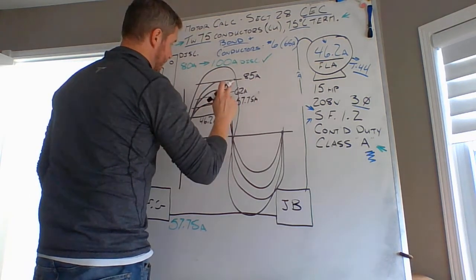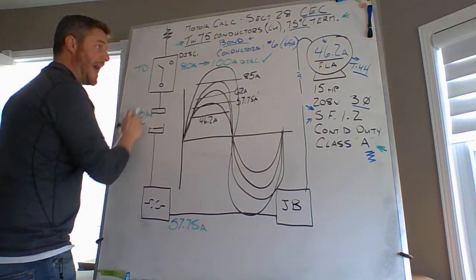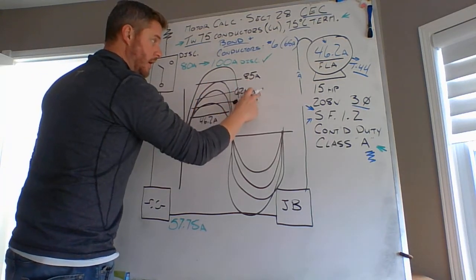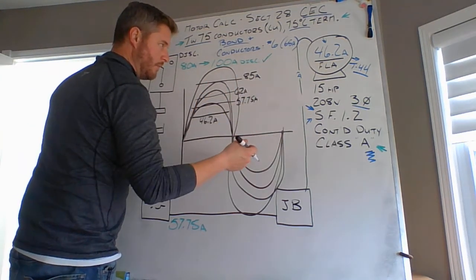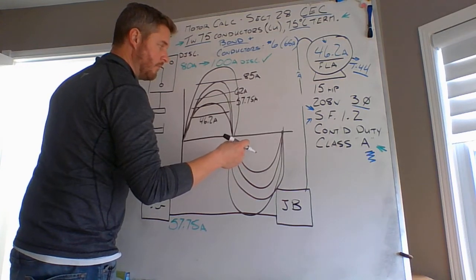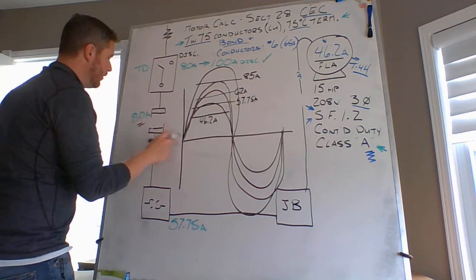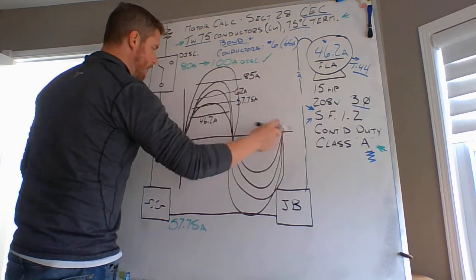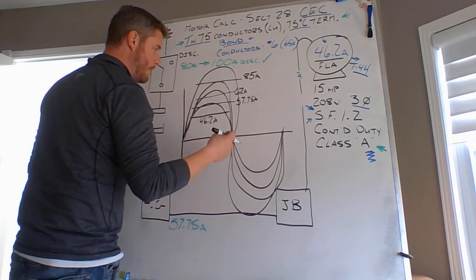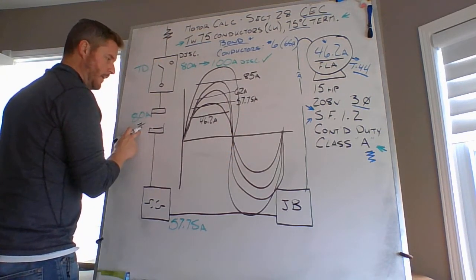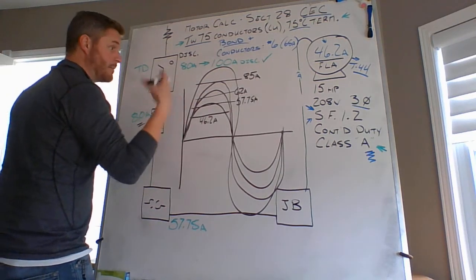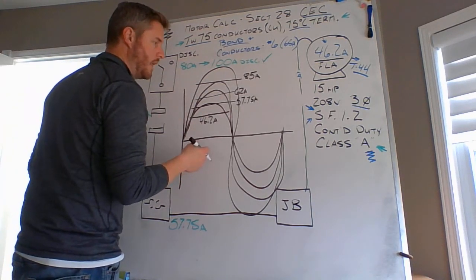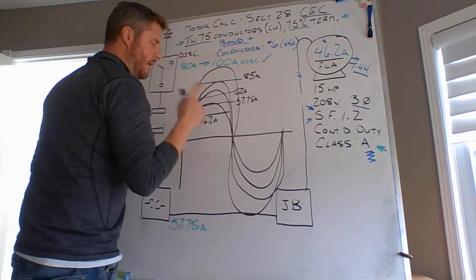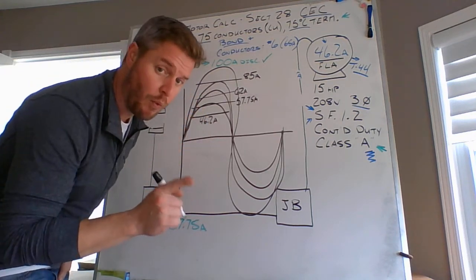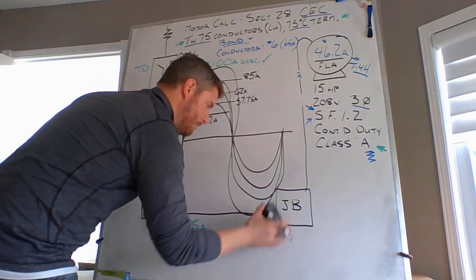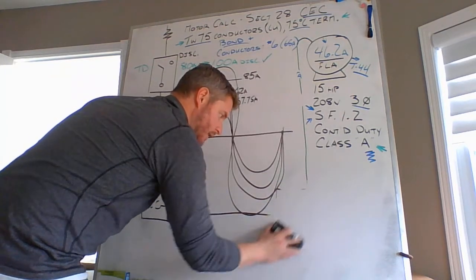It's not designed for that. So your overcurrent protection acted accordingly. And that's the inrush thing. It's a time delay fuse. It'll allow the 85 amps for a short period of time, but not forever. Those fuses will end up blowing if you draw 85 amps for an extended period of time. But here's how overcurrent actually works. I'm going to get rid of this here for a second.